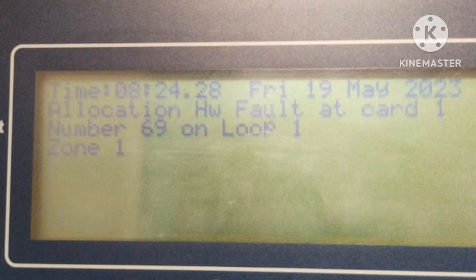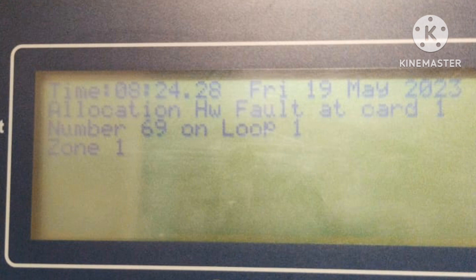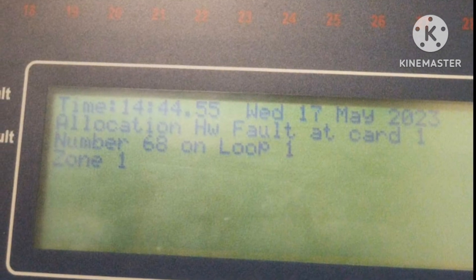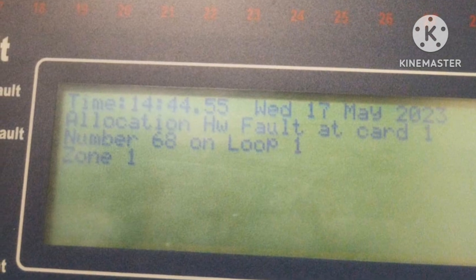The next allocation fault type is the hardware fault: 'HW fault at card 1, number 69, on loop 1.' This also appears according to loop and device number. It means the device may not be correctly fitted — it was not installed properly. We need to check the device connections or verify it is properly installed. Go to loop 1, device number 69, remove and check, then reinstall.